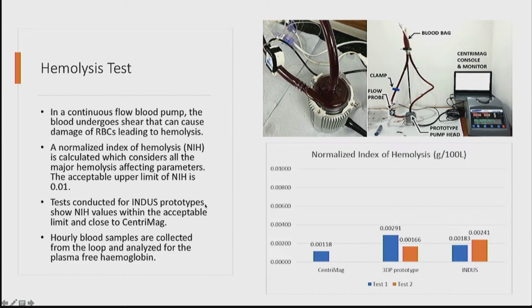So we conduct these tests where we take blood samples from the loop every 1 hour and check for the plasma-free hemoglobin present in the plasma. At the end of the test, an index is calculated, known as the normalized index of hemolysis, and for that value, 0.01 is the acceptable limit.